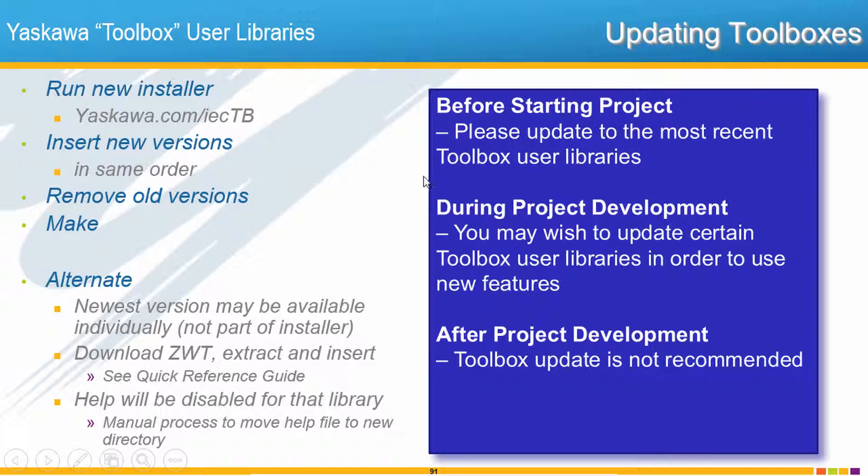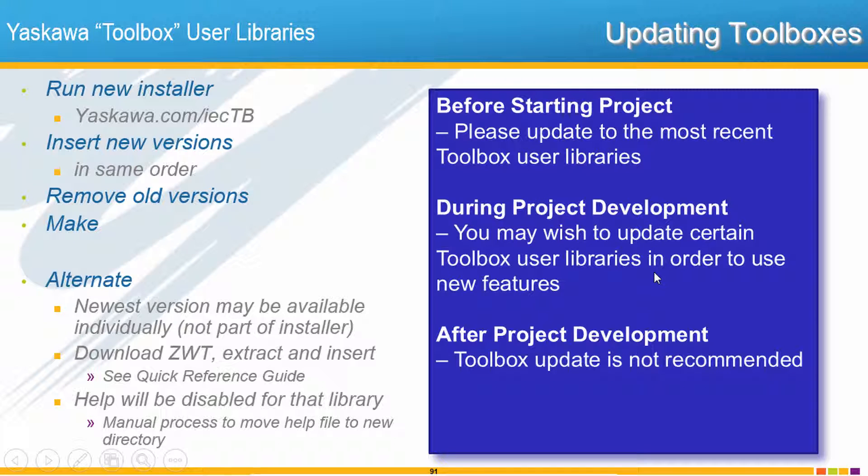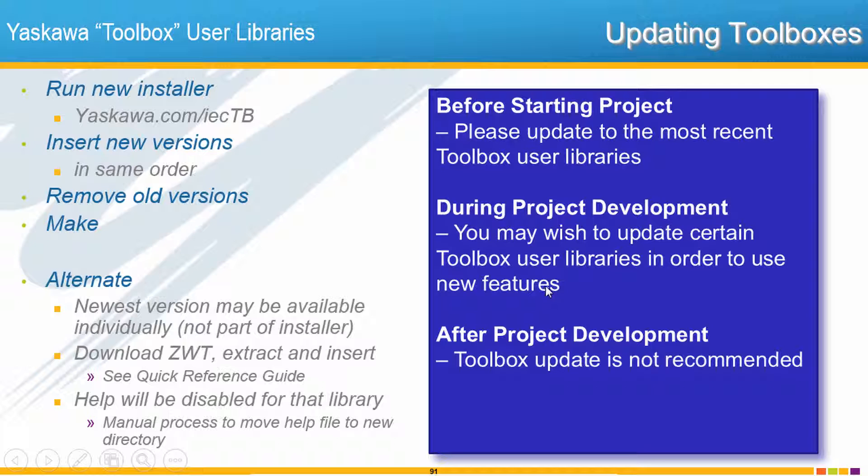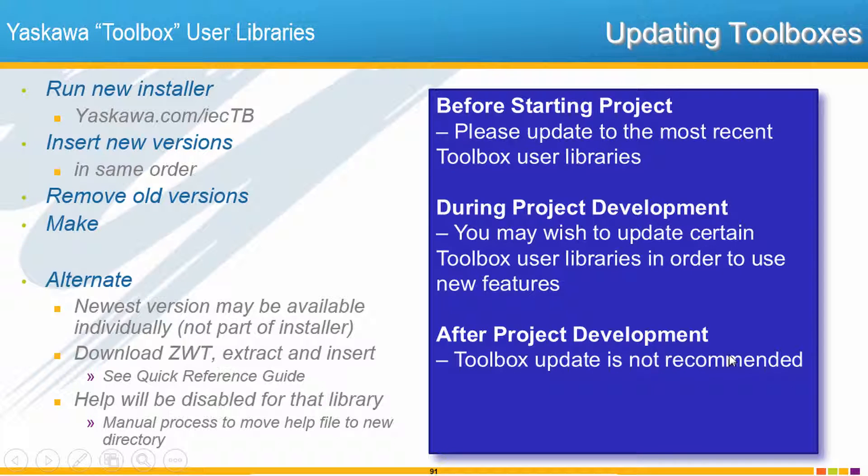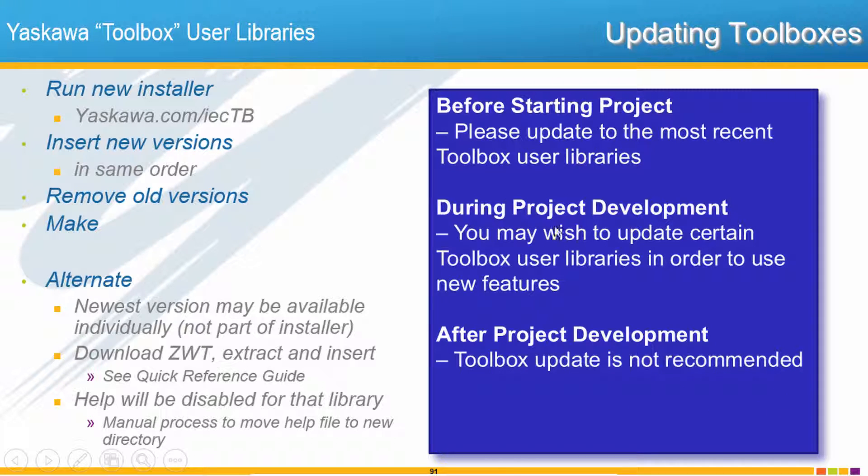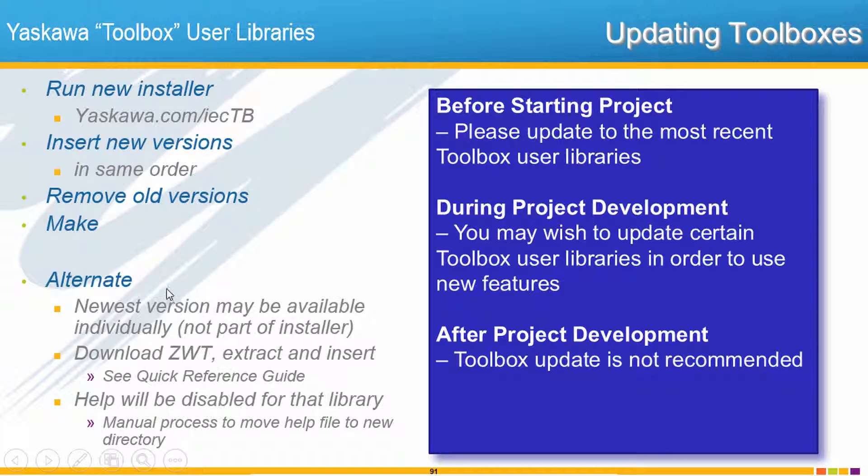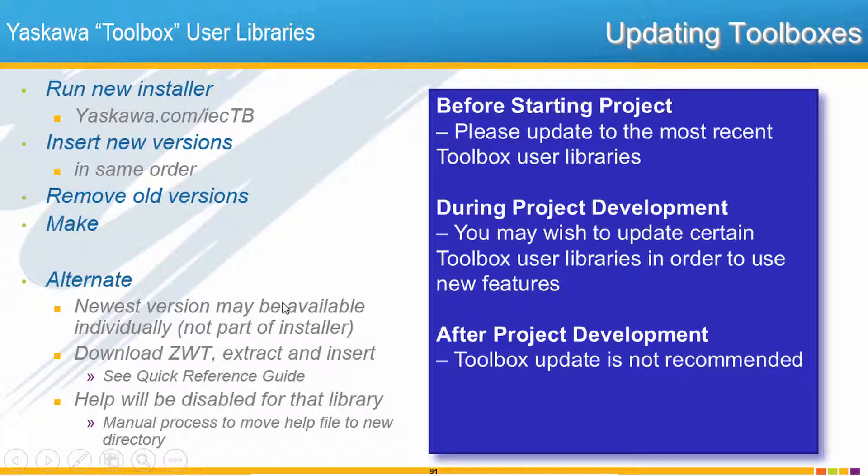If your project is in development then you may wish to update a certain Toolbox library if there's a new feature that you've found out about that you'd like to take advantage of, otherwise it's probably just easier to keep with the version that you started with. Definitely after the project's been developed and the machine is running we don't generally recommend that you go back and update all of the Toolboxes at any time, it's better just to leave the Toolboxes with the version that you developed it with. Now when you really want to be on the bleeding edge of Toolboxes realize that the newest version may not be in the installer but you could install it individually.